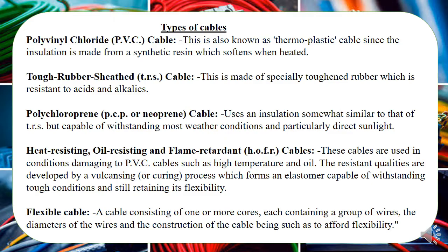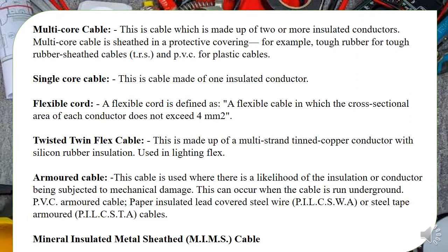We also have cables — remember, there's a difference between a cable and a conductor. We have the polyvinyl chloride (PVC) cable, the most common cable for most installation work. Then we have a similar but different version called the tough rubber sheath (TRS) cable. We also have the polychloroprene (PCP) cable and heat-resisting, oil-resisting and flame-retardant cables. Then we have flexible cables and multi-core cables — where two, three, or four cables are insulated together — as opposed to a single-core cable.